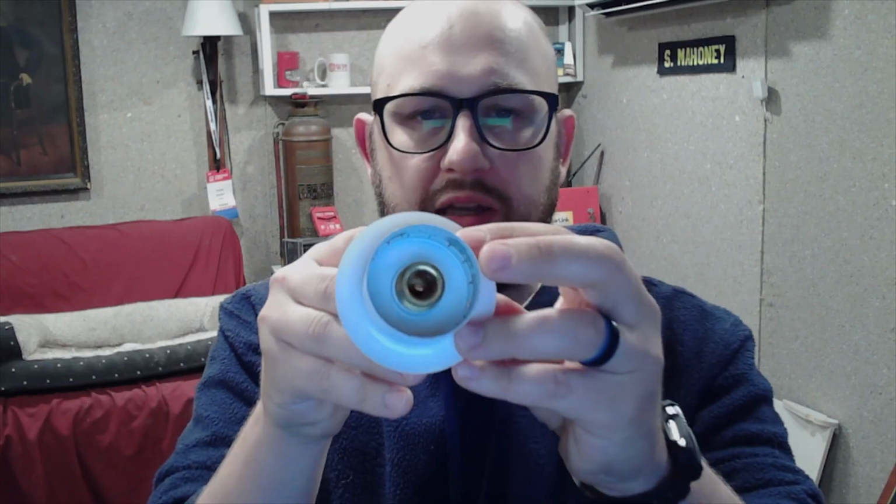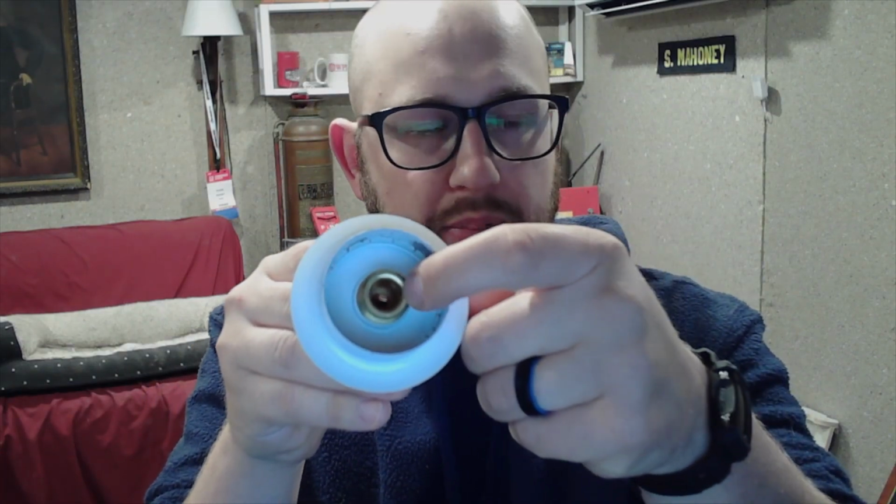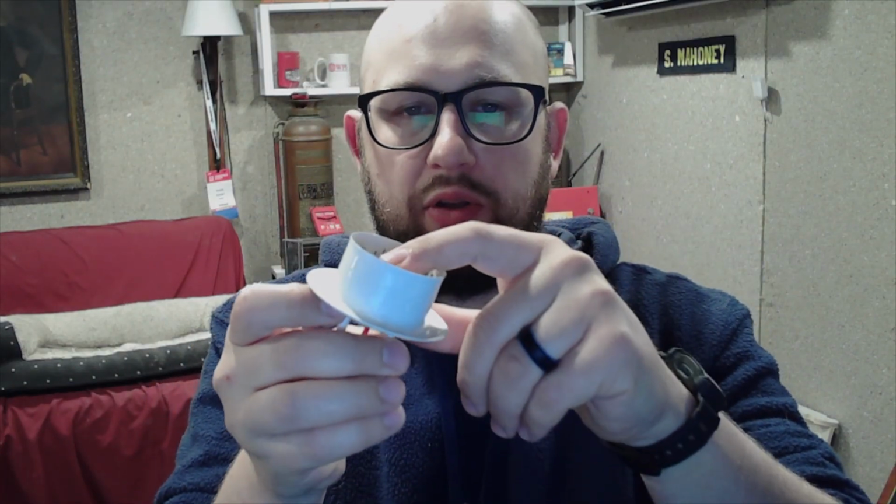And then we have here an orifice seat, a seal, and a cap. All of that is holding back the water. If we look inside, you see the cap inside of the sprinkler. That's holding back the water. So we have a cap and a seal there. And what's holding that cap and seal in place is going to be our fusible element. In this case, this is a glass bulb that is going to activate at a specific temperature.